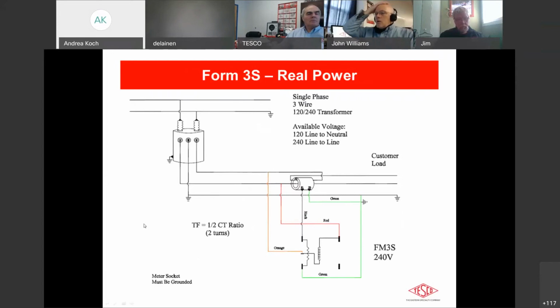All right, so another application, we go to our first transformer rated meter form. This is the simplest of the transformer rated meter forms, the 3 and the 4S. So here again, we have our 3-wire pole transformer. In this case, we're taking the voltage directly into the voltage coil. And then on this diagram, at least, we have our CT for the current application to the current coil in the meter. Here also, this is a 240 volt application for a 3S.